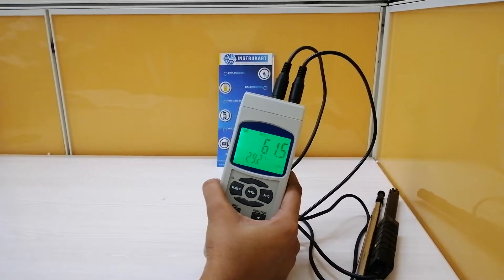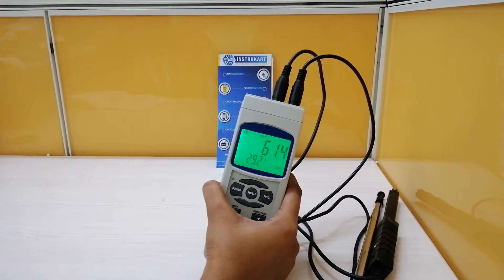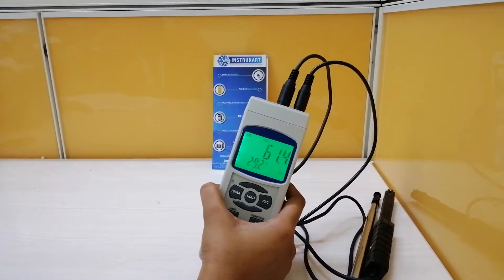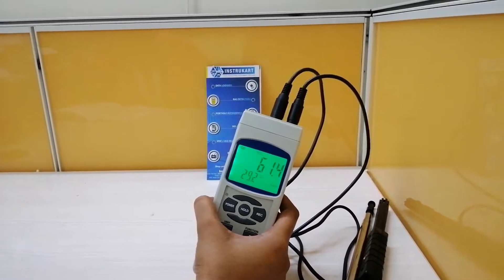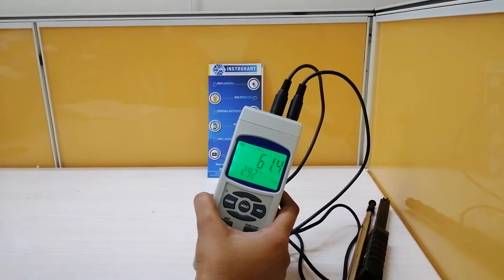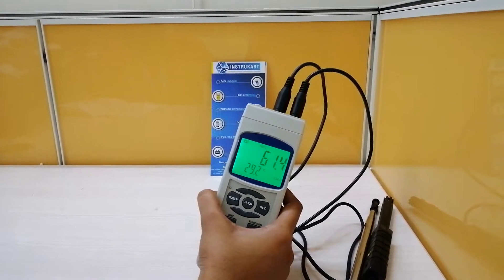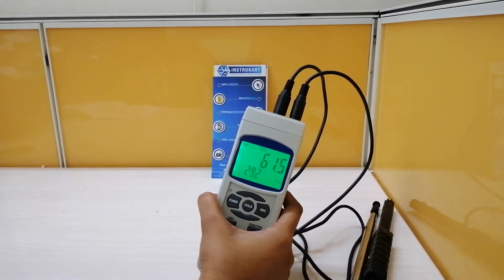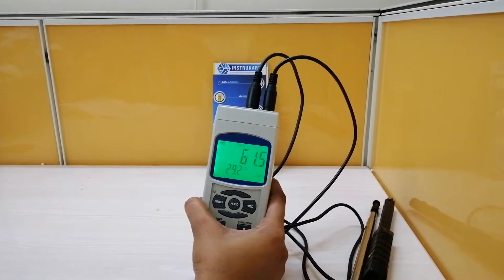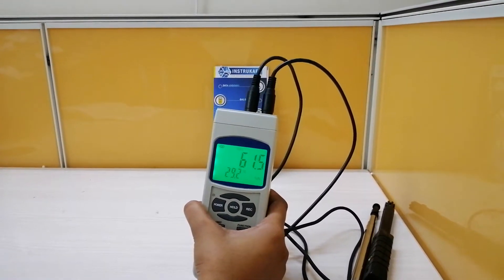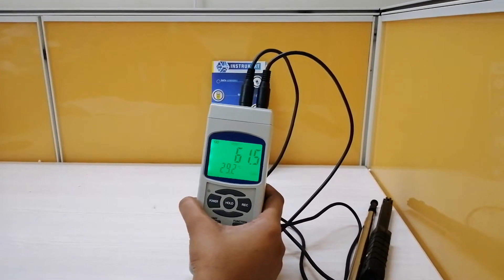As I told, it can also measure the humidity and temperature. Humidity range of 5 percent to 95 percent RH and temperature range of 0 to 50 degree Celsius. You can also measure the dew point and wet bulb temperature in both degree Celsius and degrees Fahrenheit, of range minus 25.3 to 48.9 degree Celsius for dew point and minus 21.6 to 50 degrees for wet bulb temperature.